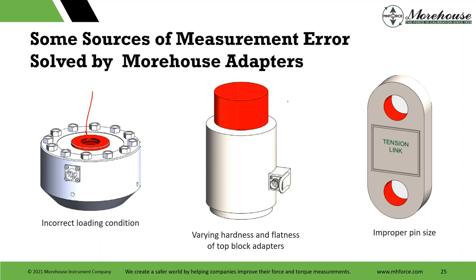Yes, really large numbers. So you definitely don't want your reference standards to be changing blocks, because your errors could be quite large, especially if you're thinking you're at 0.03 and changing top blocks is going to put in a 0.3% error. That's 10 times what you would claim.